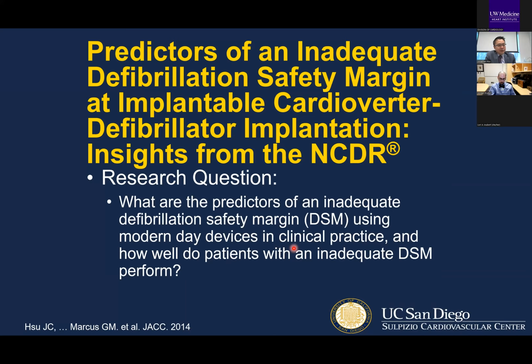When we implant an ICD, we can induce ventricular fibrillation, test that the device can sense the arrhythmia, and actually shock the patient out of it. This is usually called defibrillation testing, whether you test the threshold or how much energy is needed to defibrillate somebody.